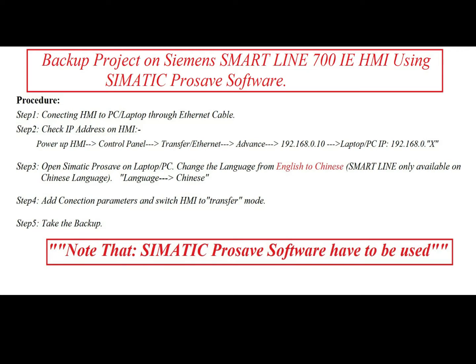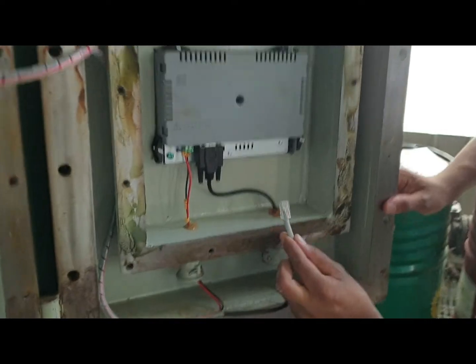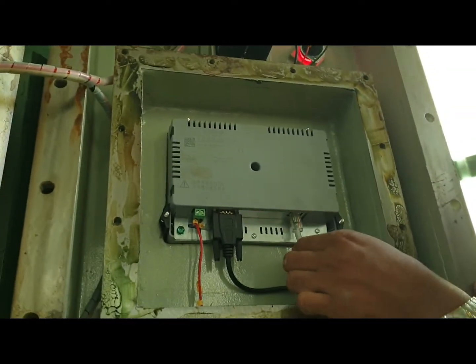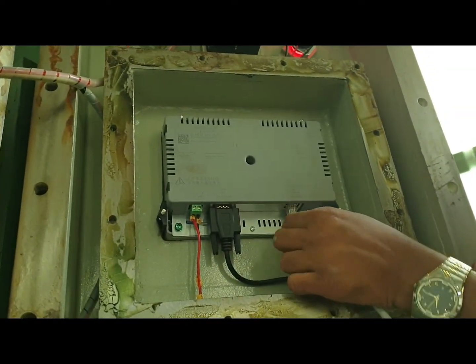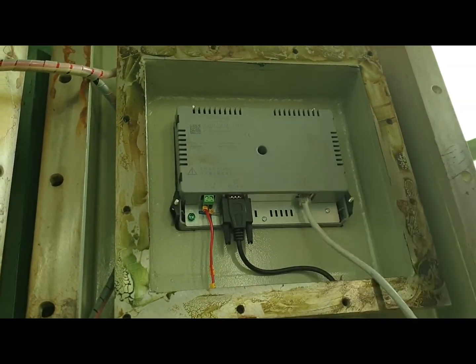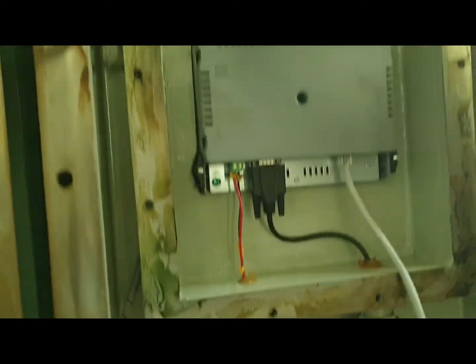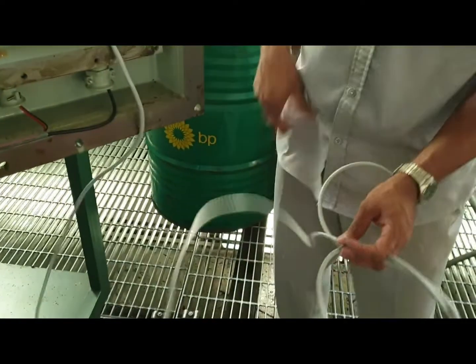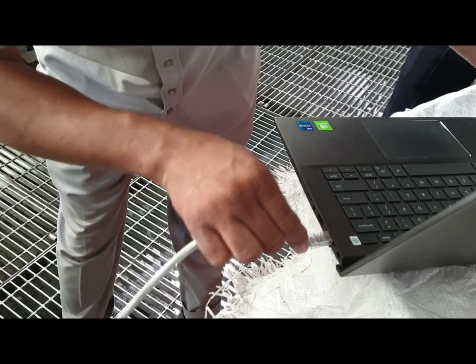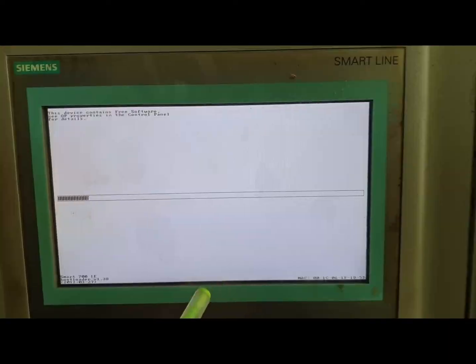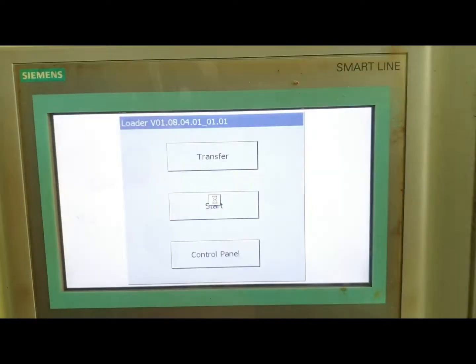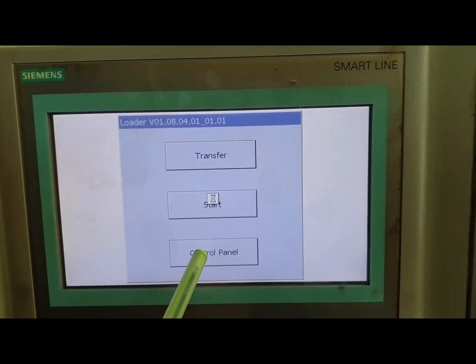Note that Siemens Prosave software has to be used. First we connect the Ethernet cable from HMI to laptop on the HMI side, then connect the Ethernet cable to PC side. Then power on the HMI.